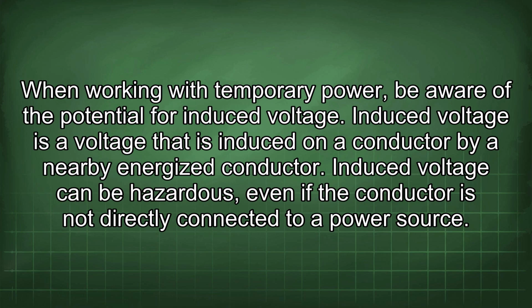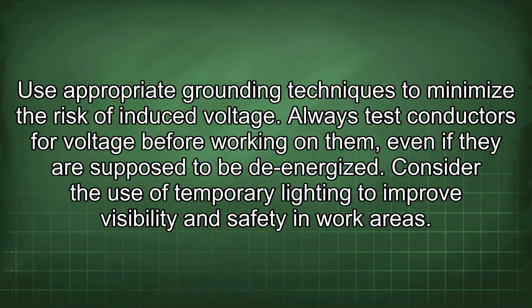When working with temporary power, be aware of the potential for induced voltage. Induced voltage is a voltage that is induced on a conductor by a nearby energized conductor. Induced voltage can be hazardous even if the conductor is not directly connected to a power source. Use appropriate grounding techniques to minimize the risk of induced voltage. Always test conductors for voltage before working on them, even if they are supposed to be de-energized.